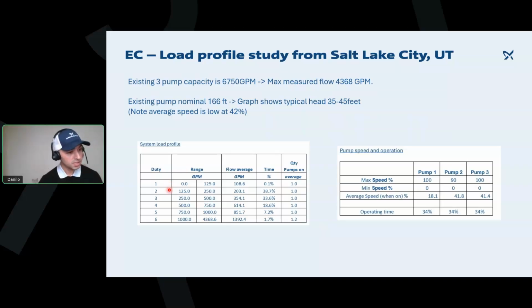So here we have 6 different types of duty conditions, right? We're going from 1 to 125 gallons, 125 to 500, and so on, all the way above 1,000. That's the average. How much time do we spend in each range here? So as you can see, most of the time we're spending within the ranges of, I want to say, 125 to 500 gallons. How many pumps are running at that time? You have one pump only.